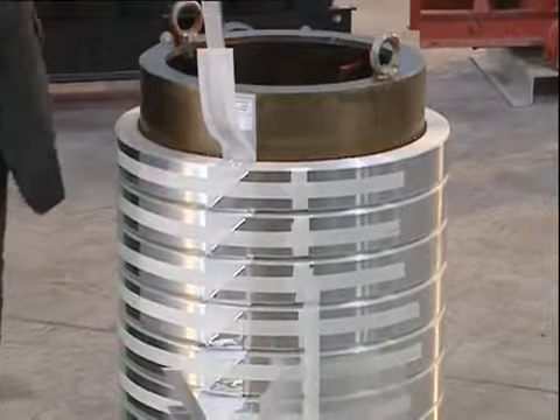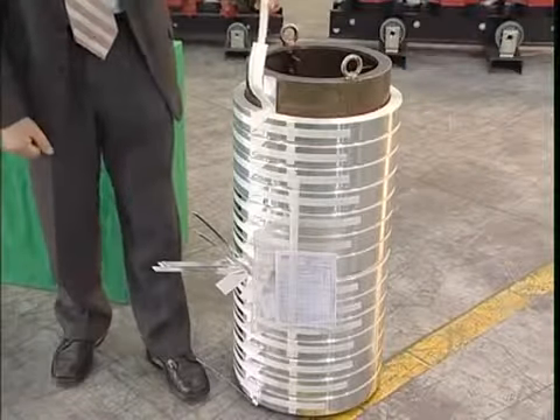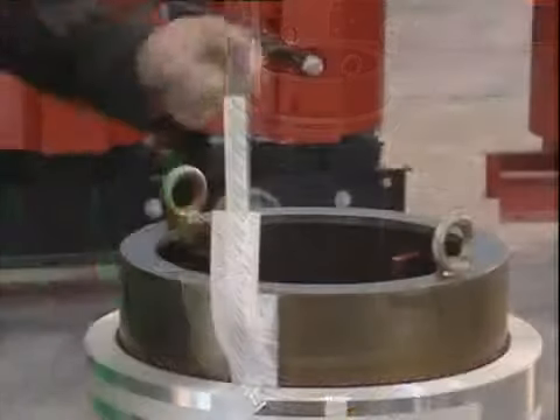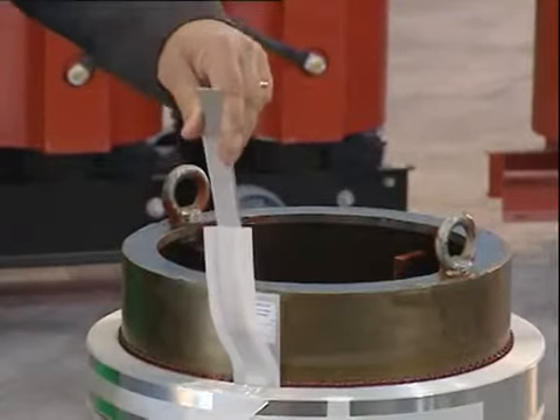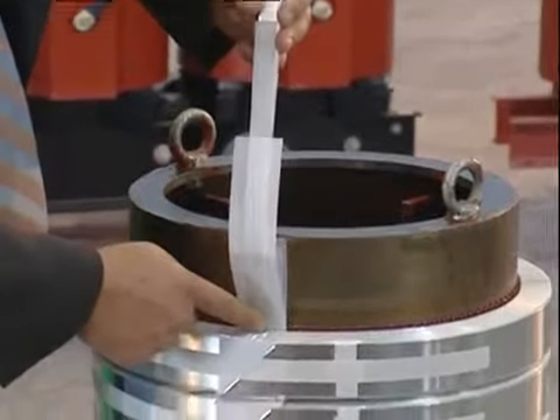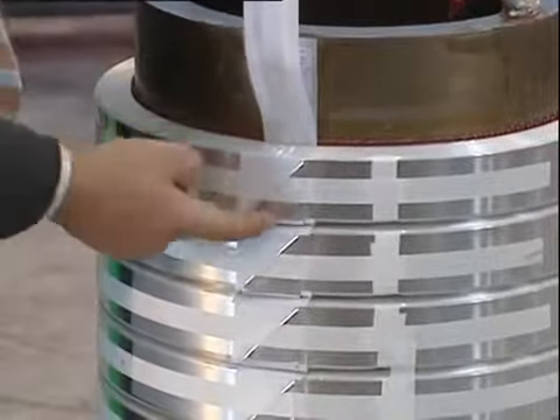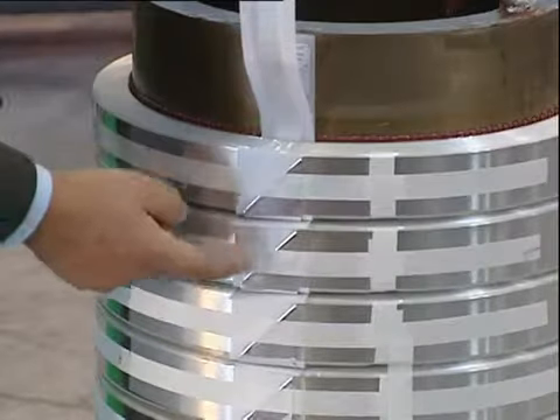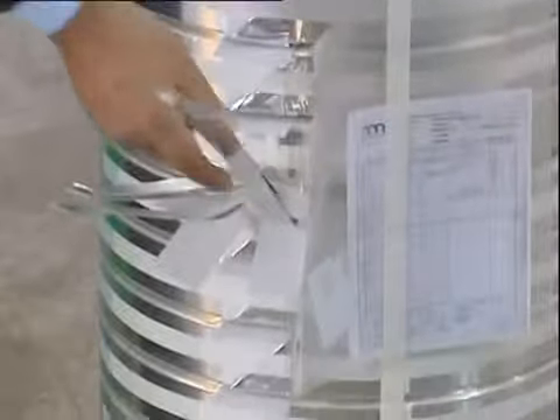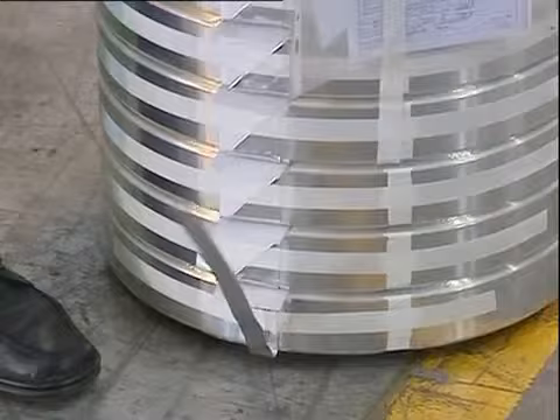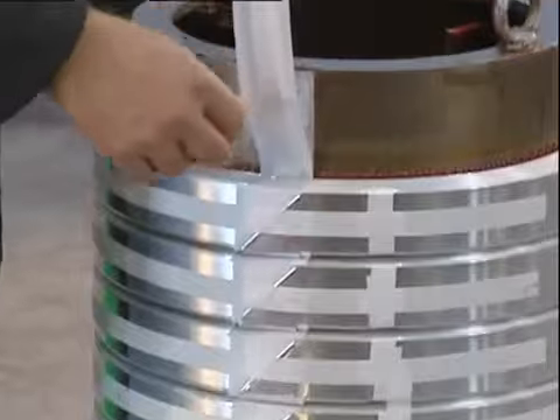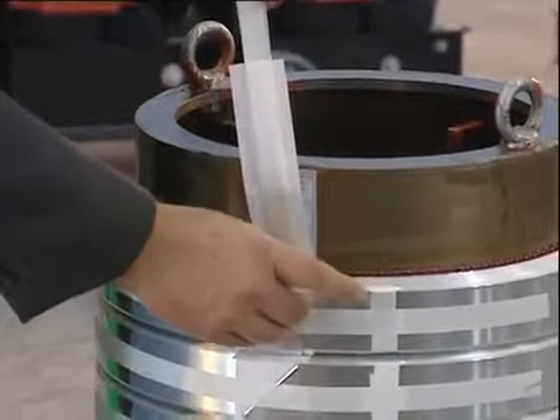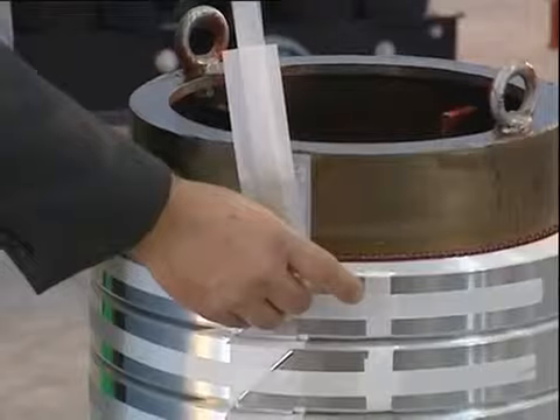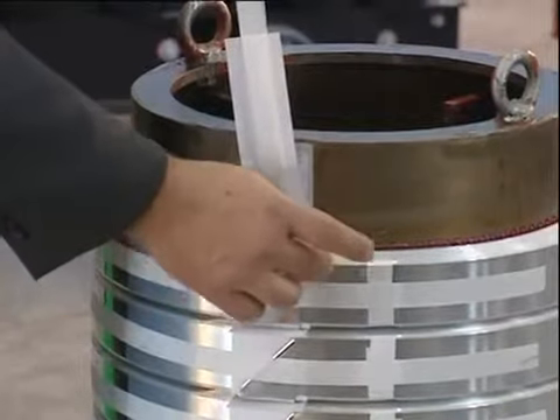Let us start immediately by showing our viewers what the winding consists of. This is the winding's input terminal, then the turns in the first section, then the series connection with the second section, and so on and so forth up to the tapping points. We then continue from the tapping points up to the output terminal. I would like to specify that the winding consists of one single turn per layer, and that every layer includes two insulating layers separating the upper turn from the lower one.